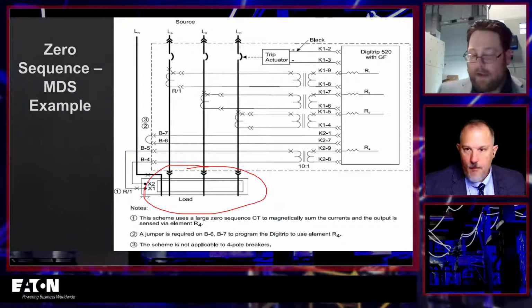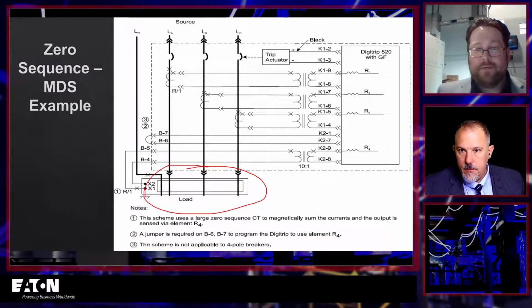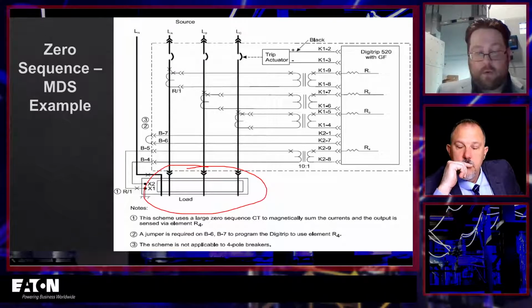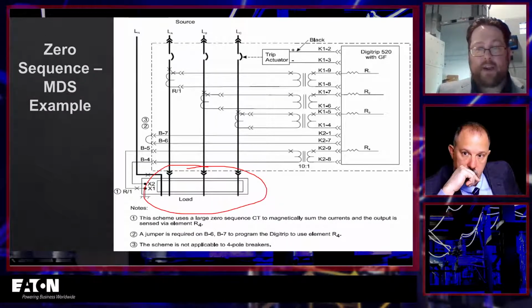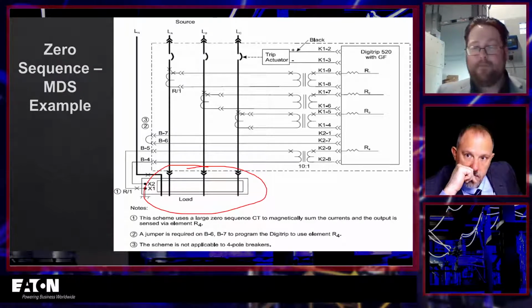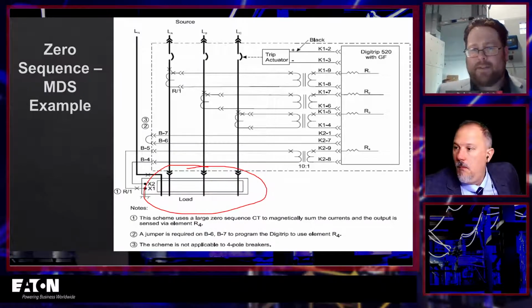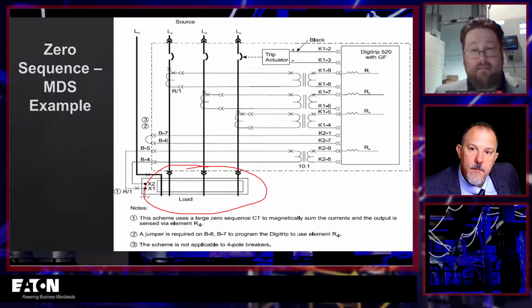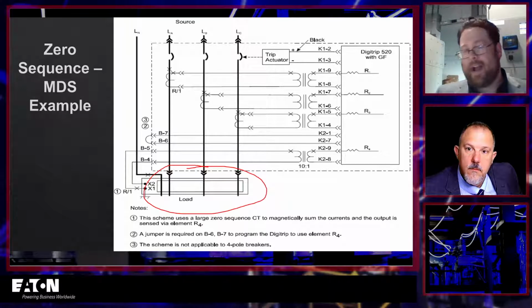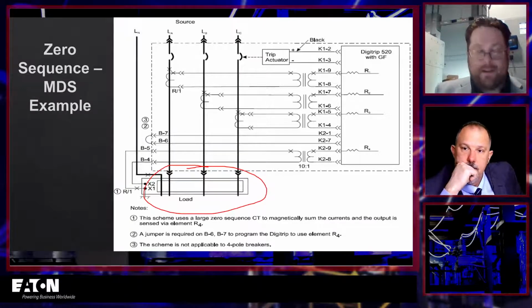But they got called out that they're having these issues with ultimately the coordination of the system. So the employee goes out and starts to really test the coordination and goes through the transfer scheme that was on the switchgear, double-ended main-tie-main, right? And finds out the transfer scheme's not quite working the way he thought it should. So he dives into it a little bit more and says, okay, I got to take your switchgear and make it electrically safe on half the switchgear.